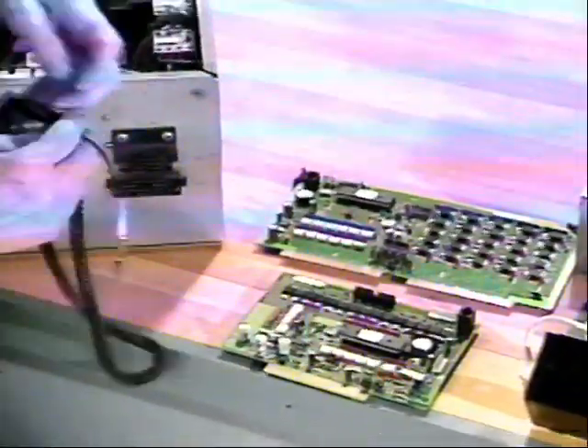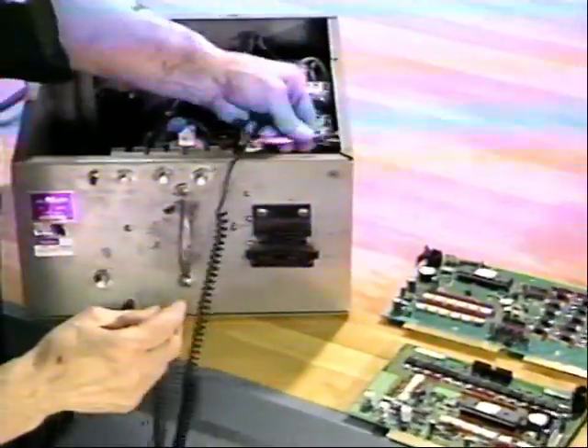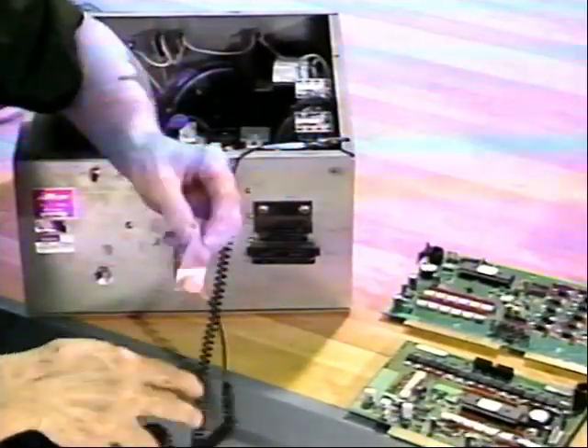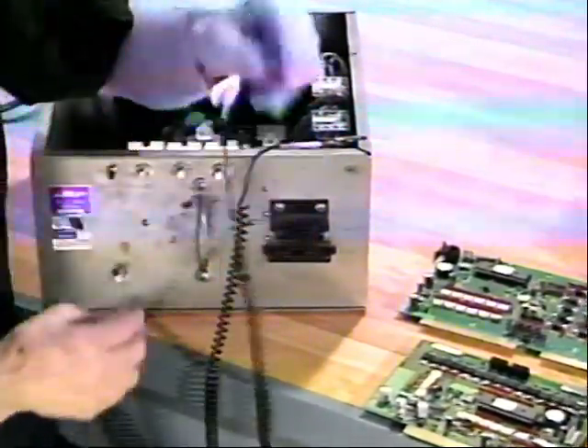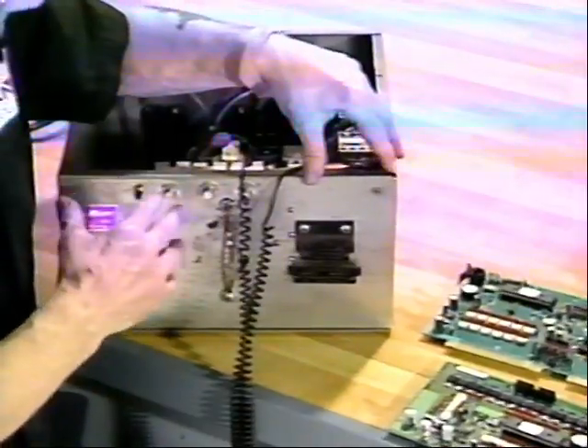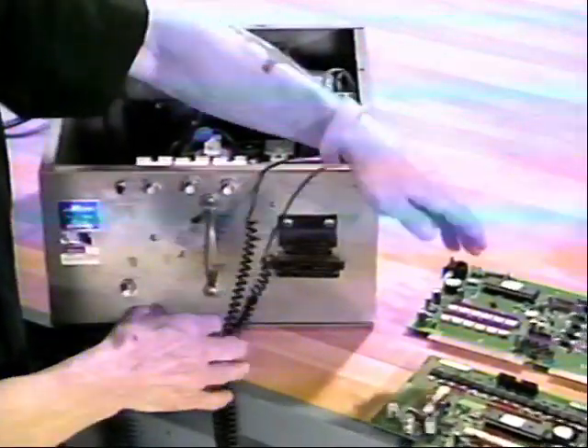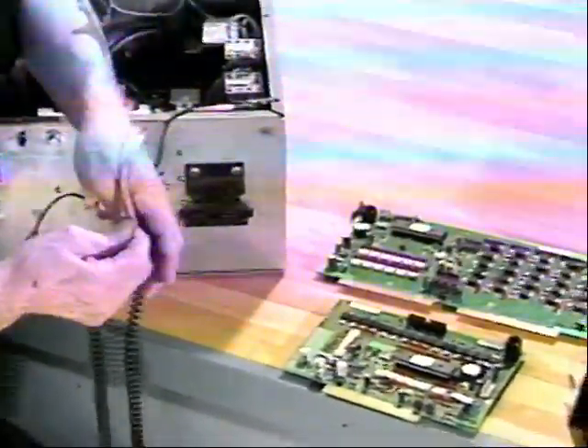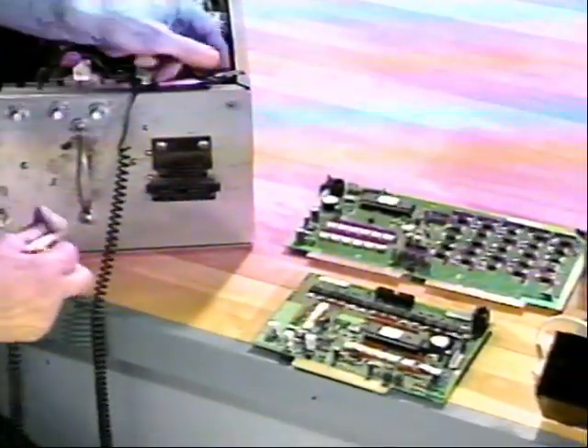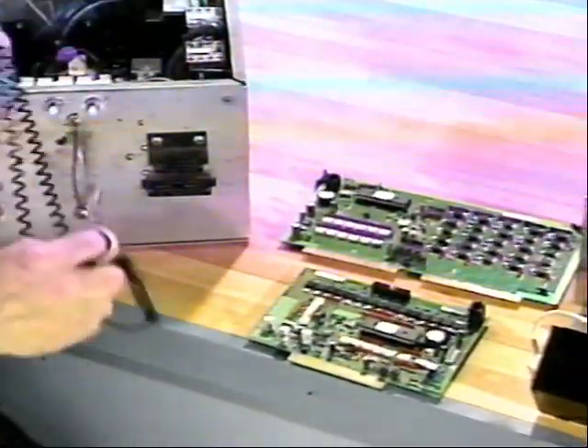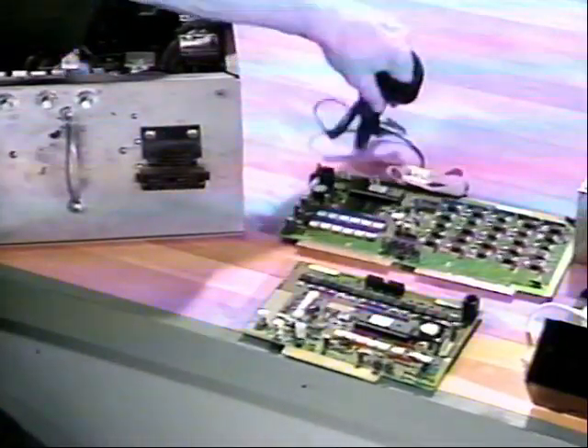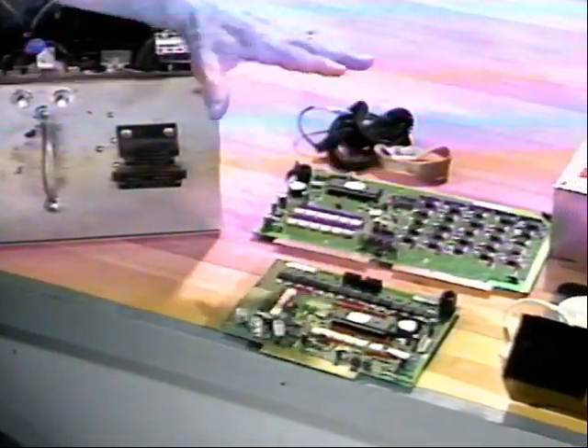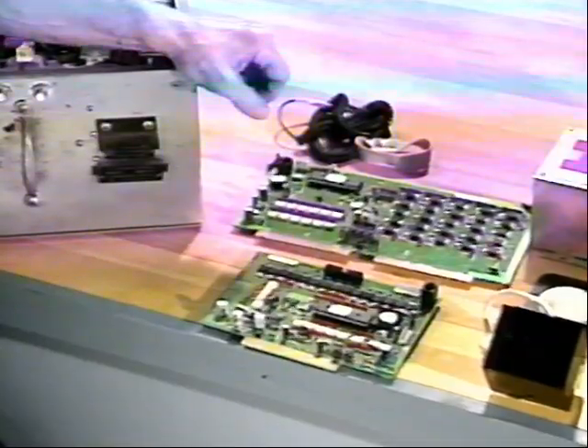When these boards are handled, the mechanic should be wearing a grounding wrist strap. This protects against possible electrostatic discharge, simply grounding oneself to the chassis so that you and the chassis are at the same potential. These circuit boards are shipped in a conductive or static bag. Once the board is taken from the bag, you should be wearing the grounding wrist strap. The board in the bag is protected; the board out of the bag is no longer protected.